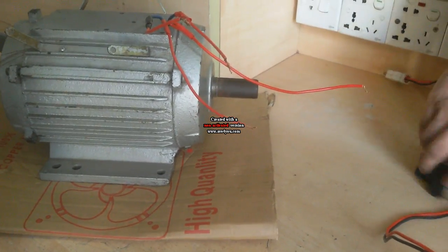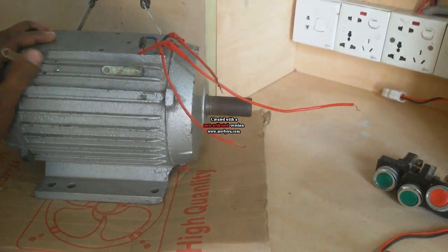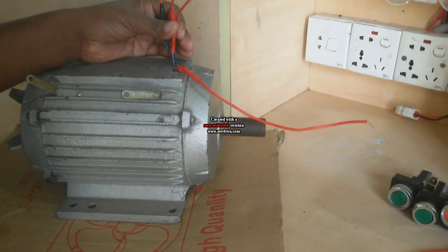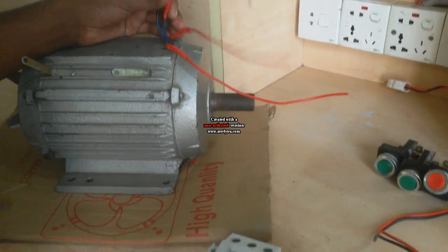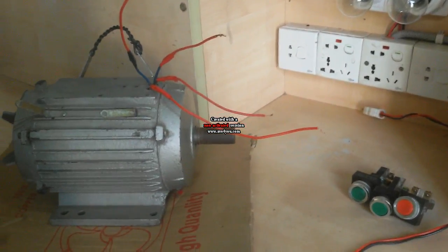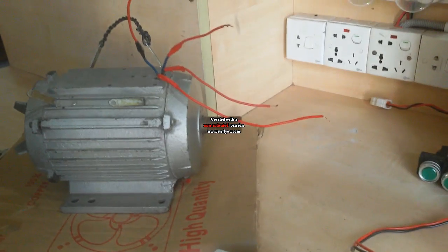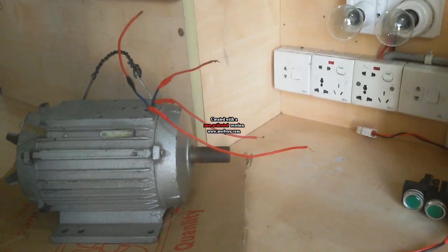Today I show how to connect a single phase motor reverse forward. This reverse forward connects this motor. I need two magnetic contactors. A single phase motor has two coils: one is the running coil and the other is the starting coil. You measure resistance. The lower resistance coil is the running coil and the higher resistance coil is the starting coil.